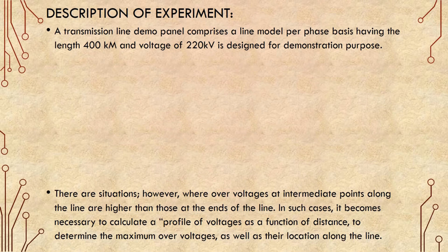In this experiment, we have a transmission line demo panel, and that is a single phase transmission line, because we are assuming that each phase is symmetrical, so we have to do only one phase analysis. Three phase will be similar to that. The transmission line in our experiment setup is a single phase demo panel of a 400 km, 220 kV transmission line.